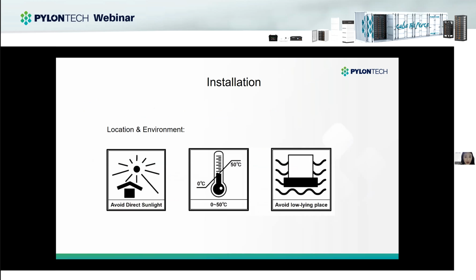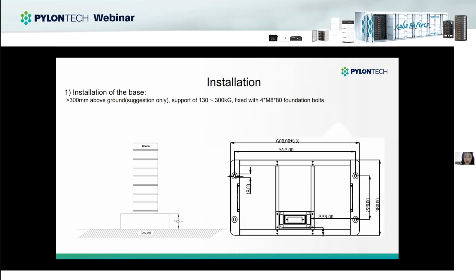And there are some requirements for the environment and the location. We recommend the battery be located in a dry place, avoiding direct sunlight. The temperature should be between 0 and 50 degrees. Avoid places that may be soaked in water or low-lying places. So the battery installation position is recommended to be 300 millimeters above the ground. And this base needs to be able to withstand the corresponding weight because the battery is not very light.